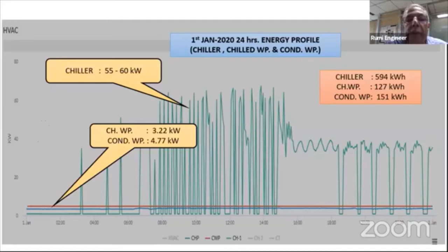At night, when my chiller is off, my chill water pump and condenser water pumps are running right from 0 hours till nearly 7 hours in the morning. And then again, it runs at a constant speed, not modulating via VFD.